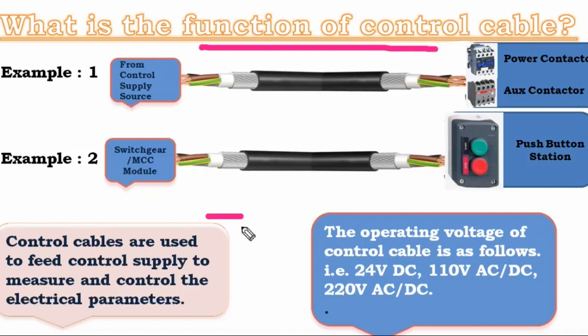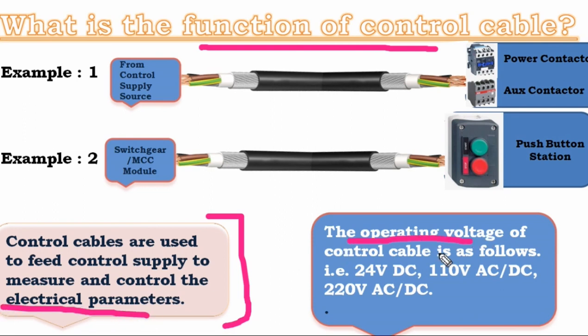What is a control cable? Control cables are used to feed the control supply to measure and control electrical parameters. The operating voltage of the control cable is 24V DC, 110V AC/DC, and 220V AC/DC — a much smaller range compared to the power cable.